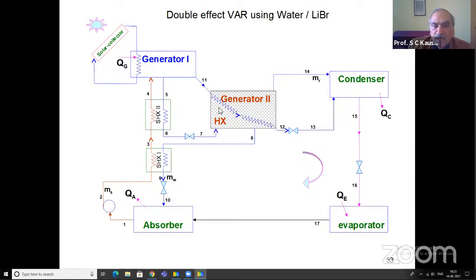Similarly, by providing triple effect generation, we can further increase the COP of the system. By providing multi-stage, multi-effect generation, a commercial vapor absorption unit with a higher COP and solar energy operation of that system is possible. One Japanese firm is commercially making these single effect, double effect, and triple effect vapor absorption systems for operation using solar energy, providing a COP nearly twice or thrice that of the single stage or single effect cycles. So it's a very promising option.